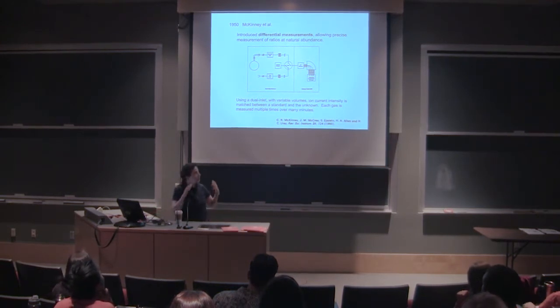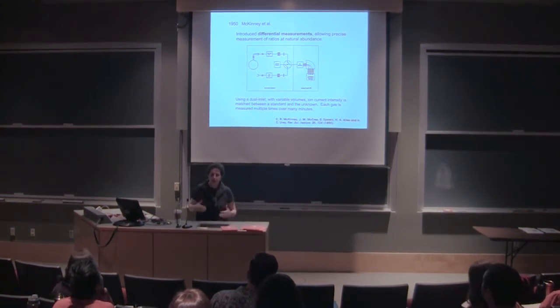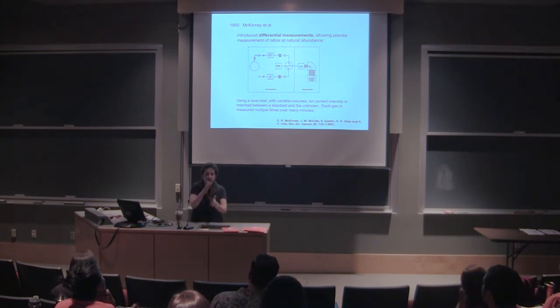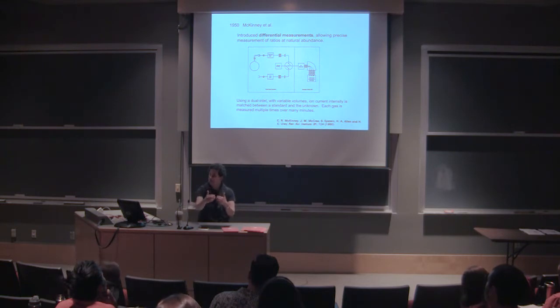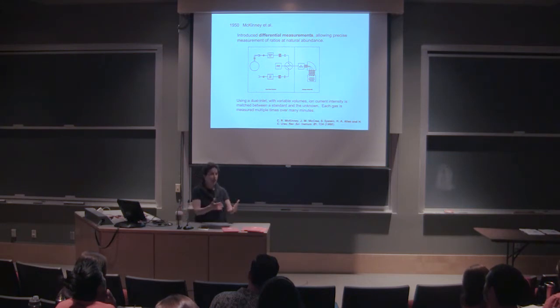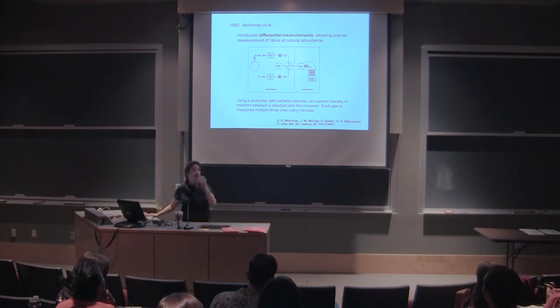What continuous flow has done is taken us away from dual inlet systems. We still do a differential measurement, but instead of back and forth we measure one material, then sometime later another, and make the comparison across time. For that to be possible we needed more stable electronics and we needed to develop plumbing and gas management to accommodate the flow of helium or whatever carrier gas is used — and that was successfully worked out starting in the 1980s and continuing to today.